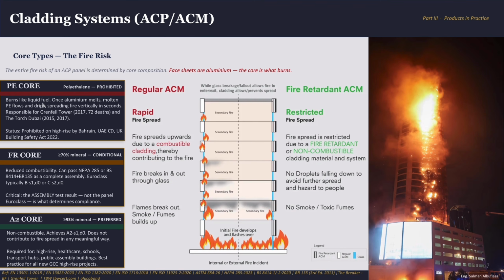The ACP is typically a polyethylene core, plastic, essentially liquid fuel wrapped in thin metal sheets. Once aluminum melts, molten PE flows and drips, spreading fire vertically in seconds. Responsible for Grenfell Tower and the torch in Dubai. It's now prohibited on high-rise buildings by Bahrain, UAE, the UK Building Safety Act 2022, and I think by the majority of local fire codes.